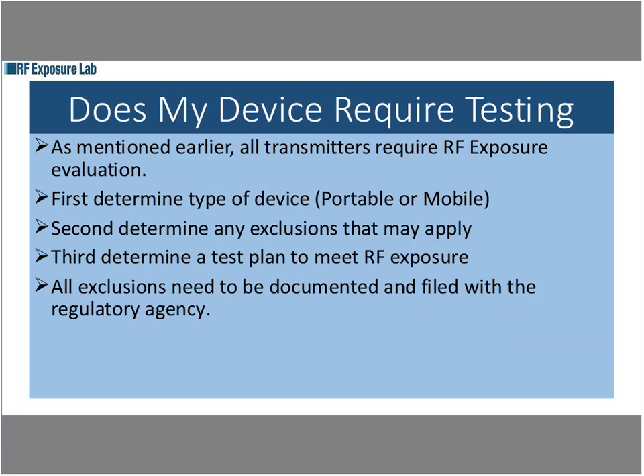As mentioned earlier, all transmitters require RF exposure requirements or evaluation. So the first thing you want to do is determine the type of device you have, whether you're a portable device or a mobile device. And then the second is to determine if there are any exclusions that may apply. You want to take into account any duty cycles you have, if you've got low power, if there's exclusions based on the distance the antenna can be maintained from the body. You want to get all of those exclusions done first, because if you can avoid SAR testing, you want to avoid it as much as possible, because depending on the device, sometimes it can be very difficult to get them to pass the requirements.